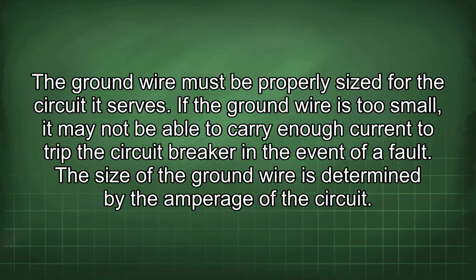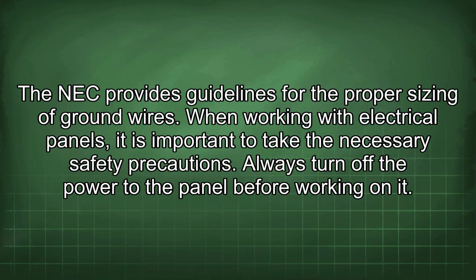The ground wire must be properly sized for the circuit it serves. If the ground wire is too small, it may not be able to carry enough current to trip the circuit breaker in the event of a fault. The size of the ground wire is determined by the amperage of the circuit. The NEC provides guidelines for the proper sizing of ground wires.